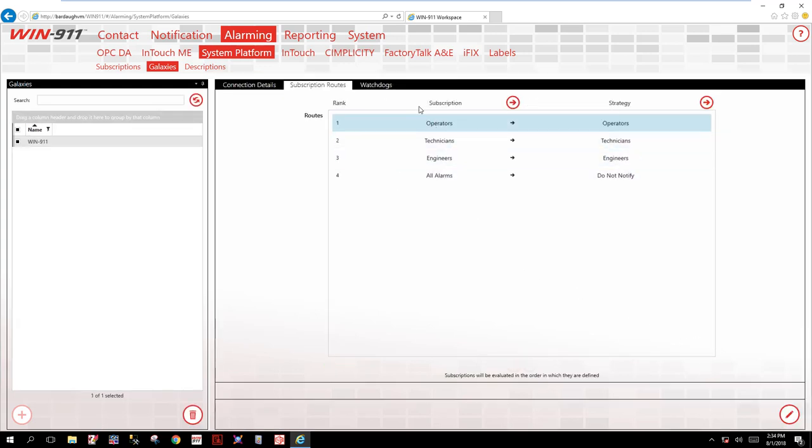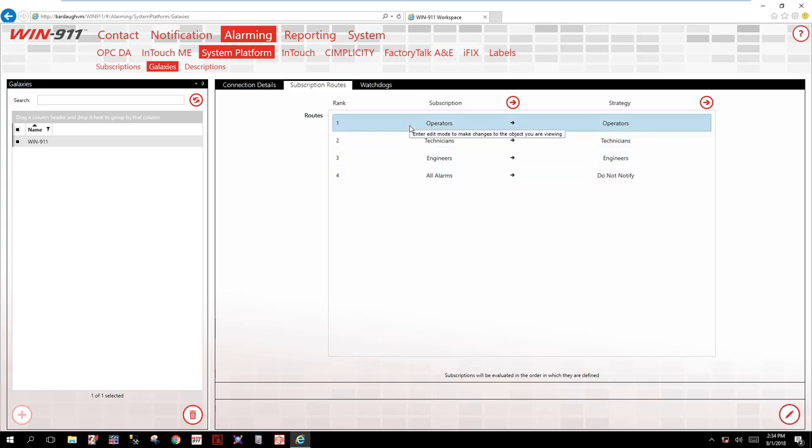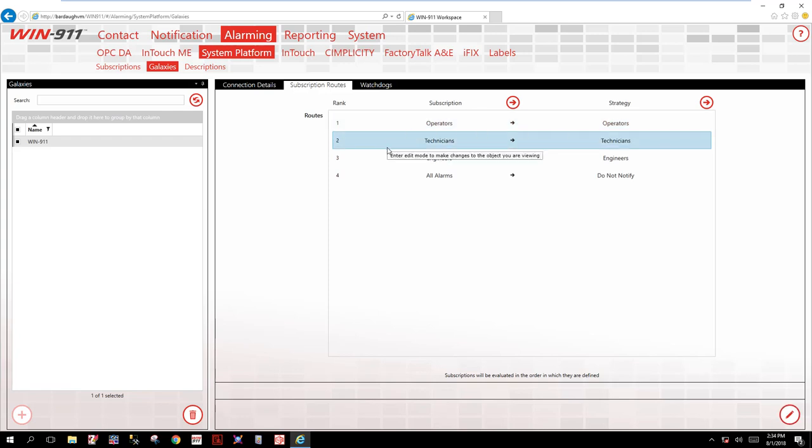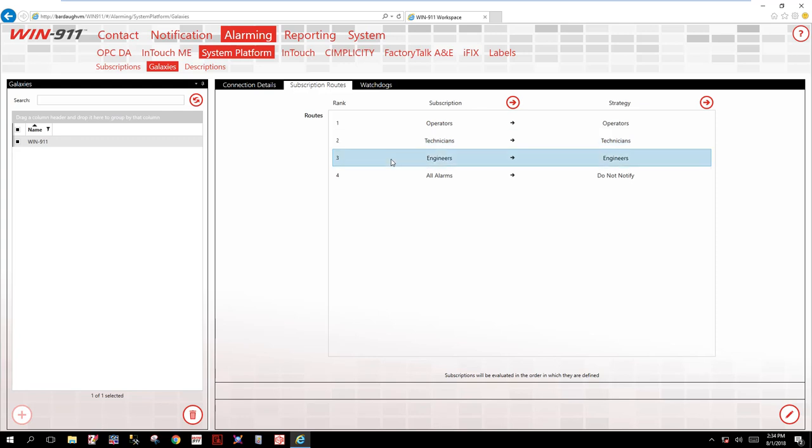Now running down the list, as alarms come in they're going to check sequentially down here. So it will check: does this alarm meet this criteria, meaning does it have photo eye or jam? Let's say no, it will move on. Does it have the criteria for technicians, which is the area of CMPSCR? Let's say no. Finally, it will go down to engineers and check to see: does this have a priority of 955 to 980? Yes, it does. So start off a strategy called engineers. This strategy will point to a tactic which is a call list of people.